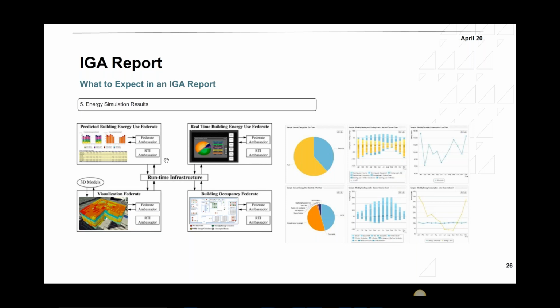And then I would put my energy conservation measures into the software. Let's say I'm changing the chiller - so I had in the baseline model a chiller with an efficiency of, let's say, 1.7 kilowatt per ton, an air-cooled chiller. And I'm putting a new air-cooled chiller, maybe with efficiency of 1.4 kilowatt per ton at 46 degrees C, or 1.3, whatever it is. I put that input and then rerun the model to check what is the effect on energy consumption.